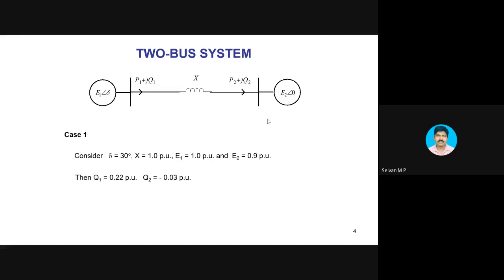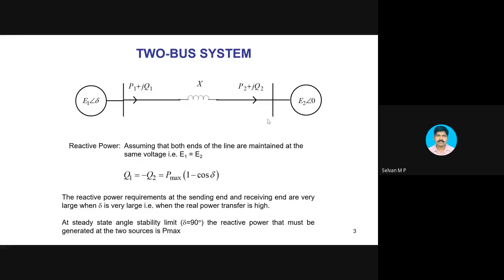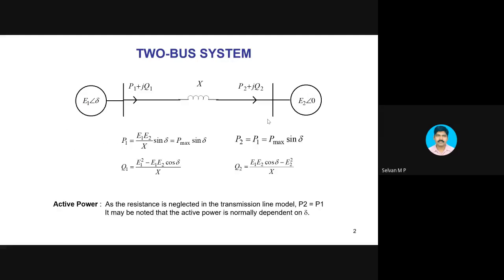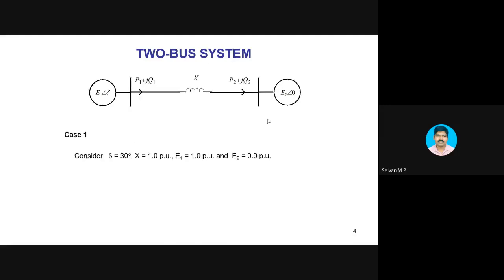Okay, now if I use these values and evaluate the value of Q1 and Q2 by utilizing these equations, I will get Q1 as 0.22 per unit and Q2 as minus 0.03 per unit. So what does it indicate? You please tell me. Q1, 0.22 per unit. 0.22 per unit of reactive power flows from this machine into this transmission line.